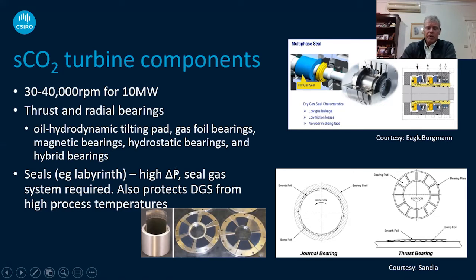The seals have maybe 25 to 30 megapascals of pressure inside the unit and ambient pressure outside, so you've got a very high delta P, and you need a very good sealing arrangement to keep the CO2 from leaking out too much. Typically that will require a seal gas system, which can also protect the dry gas seals from the high process temperatures.